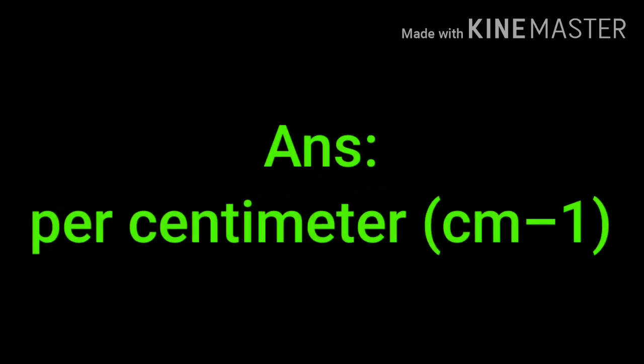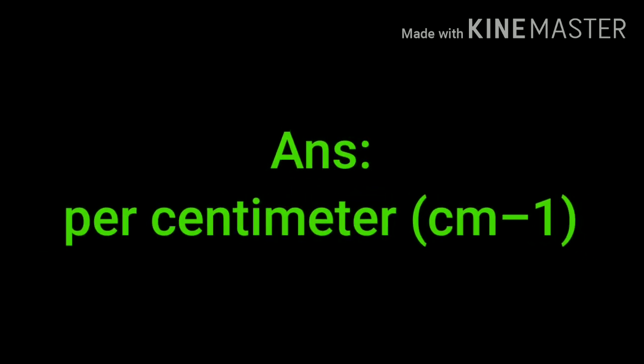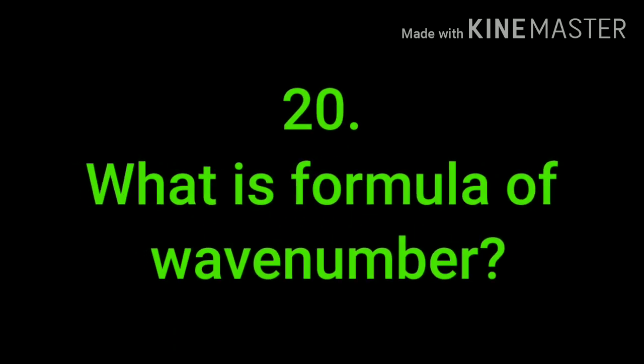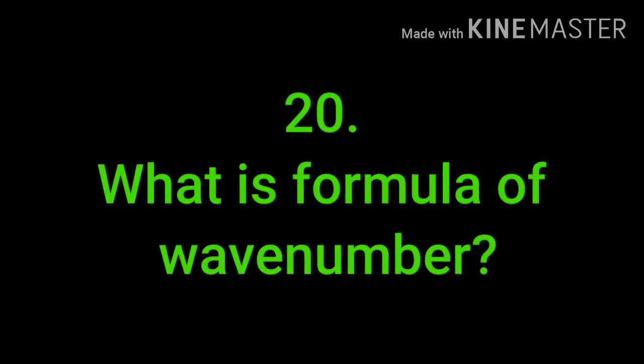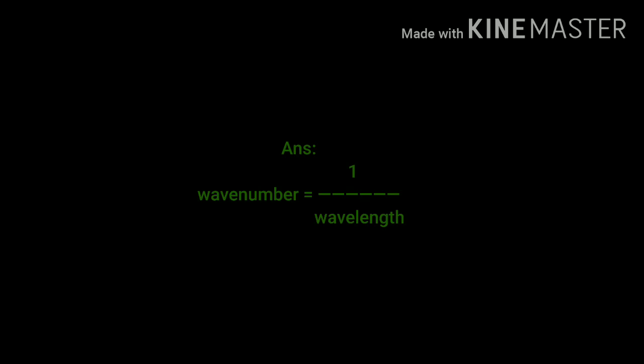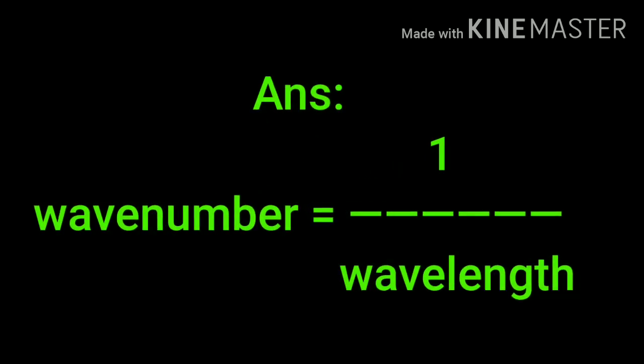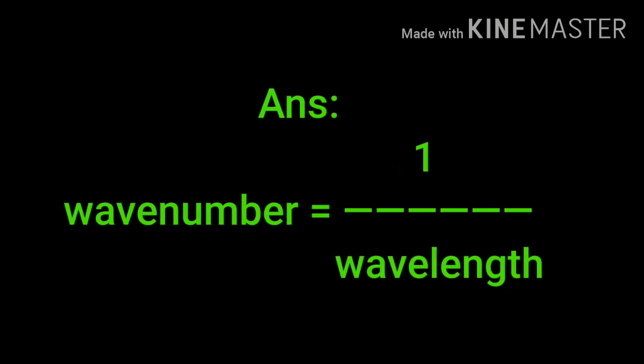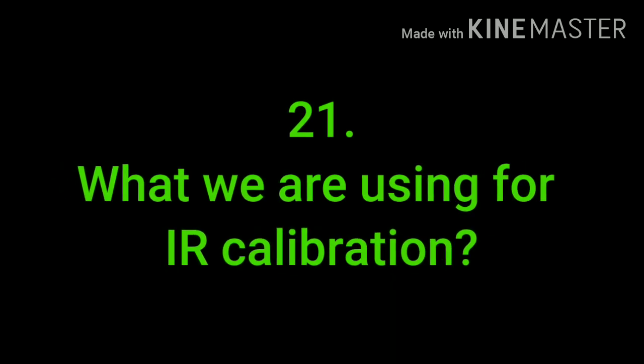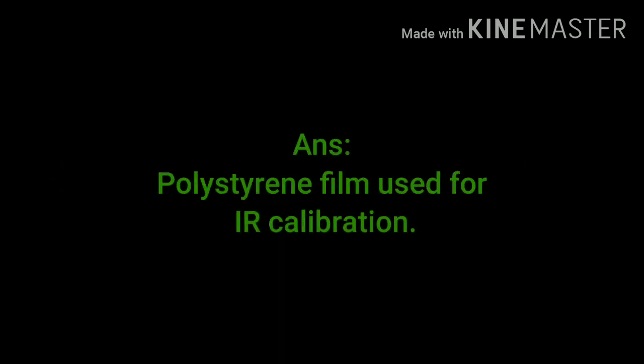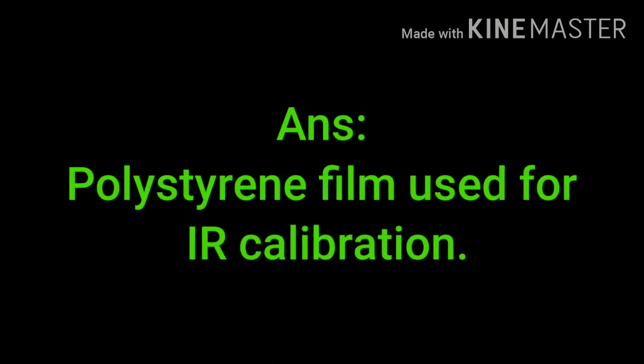What is the measuring unit of the IR spectrum? The measuring unit is wavenumber, in cm⁻¹. What is the formula for wavenumber? The wavenumber formula is 1 divided by the wavelength. What do we use for IR calibration? For IR calibration, a polystyrene film is used.